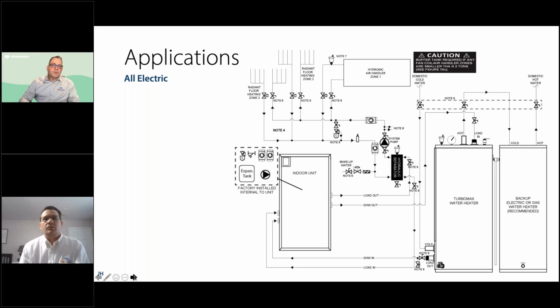We can cycle for the smaller radiant zones, and then we're saving some costs, but also a lot of space in the mechanical room. So we'll have piping with the internal pump, variable speed pump, over to the hydraulic separator, and then our system pump is what provides fluid flow to the radiant zones and/or hydronic air handling systems.